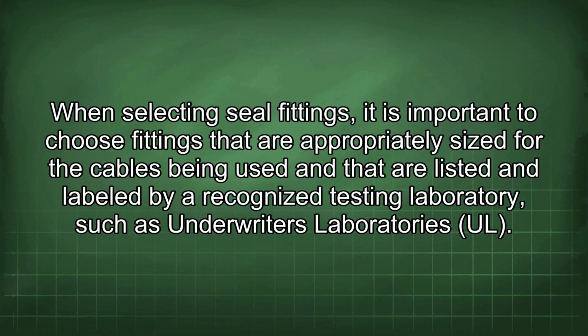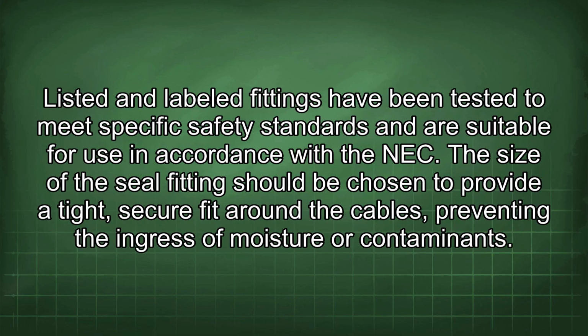When selecting seal fittings, it is important to choose fittings that are appropriately sized for the cables being used and that are listed and labeled by a recognized testing laboratory such as Underwriters Laboratories, UL. Listed and labeled fittings have been tested to meet specific safety standards and are suitable for use in accordance with the NEC. The size of the seal fitting should be chosen to provide a tight, secure fit around the cables, preventing the ingress of moisture or contaminants.